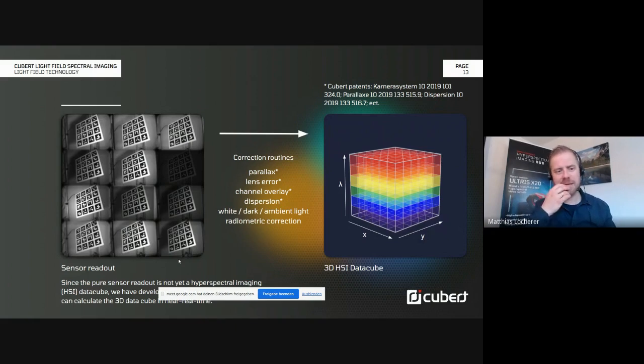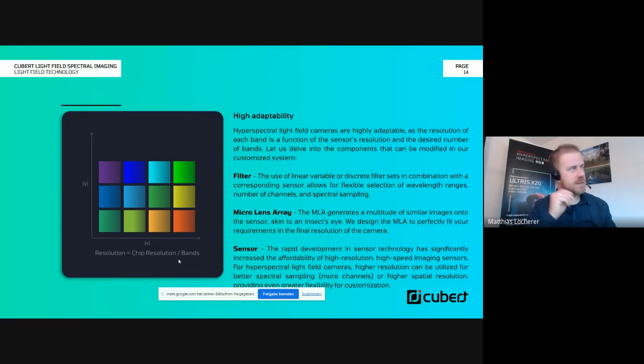The parallax, or this light field approach, is also the reason why you cannot simply mount a common lens on top of the camera to get different fields of view. But let me point that out a little bit later. A nice side effect of this approach is that it has a very high adaptability.